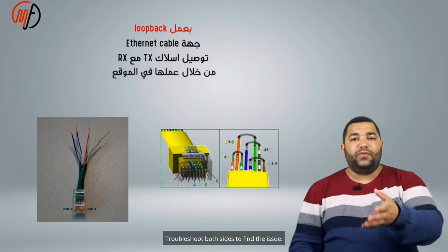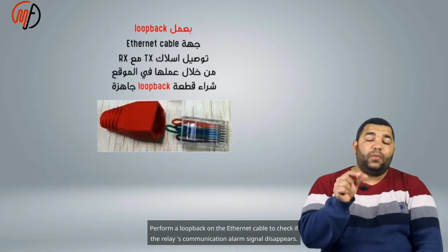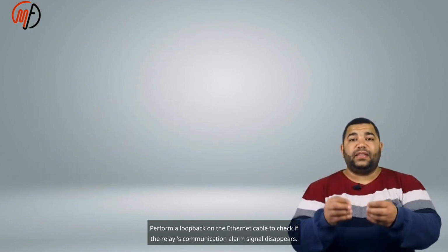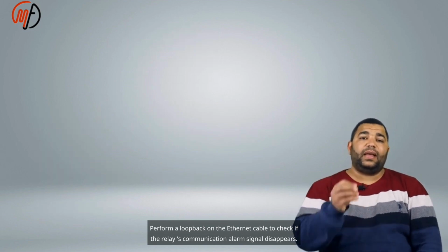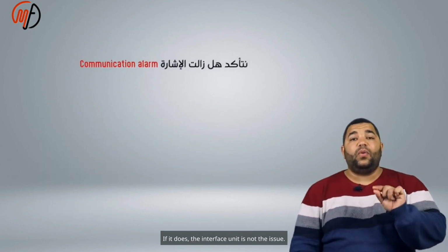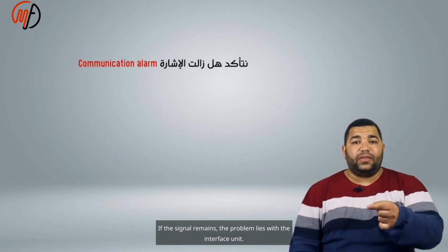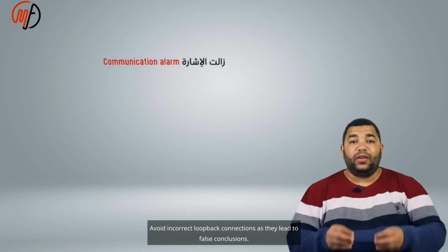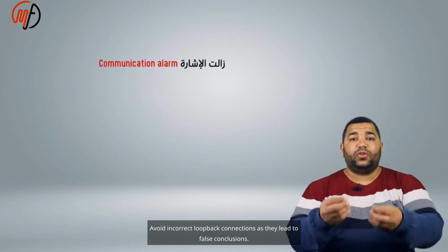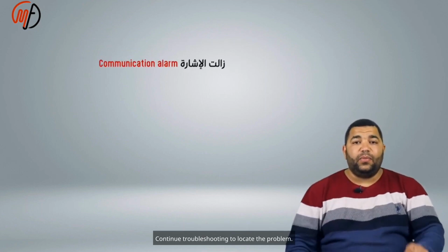Troubleshoot both sides to find the issue. Perform a loopback on the Ethernet cable to check if the relay's communication alarm signal disappears. If it does, the interface unit is not the issue. If the signal remains, the problem lies with the interface unit. Avoid incorrect loopback connections as they lead to false conclusions. Continue troubleshooting to locate the problem.